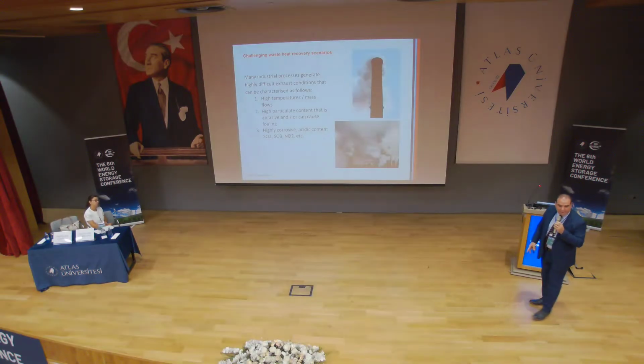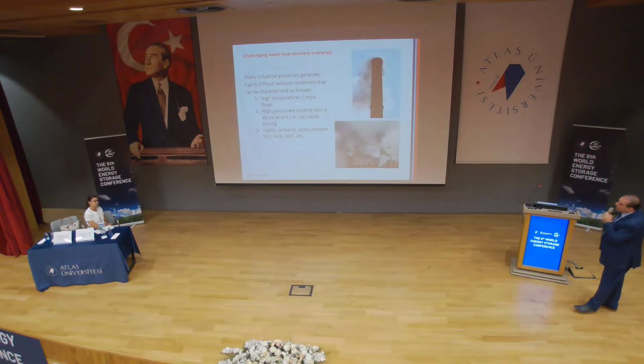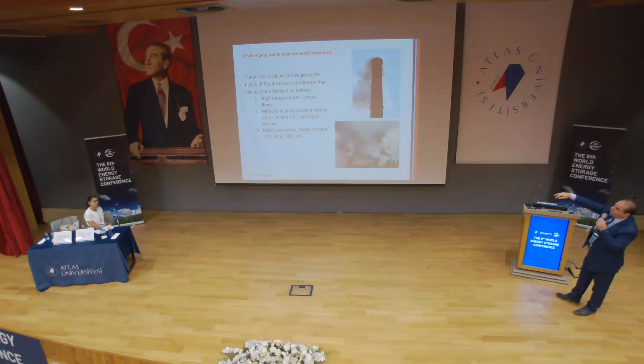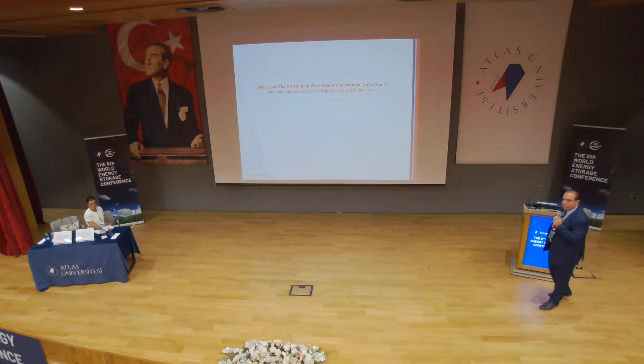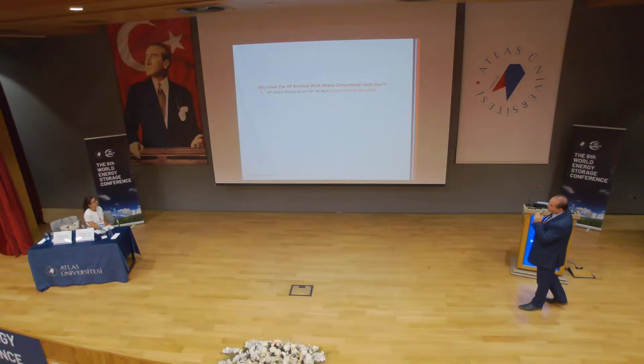So as scientists and engineers, we have to do something to address that. We use this technology to address them, because we can keep the wall temperature inside the heat exchanger uniform in the hot region, for example, meaning I don't have cold spots. When you have cold spots, you end up with acid condensation. We don't have that here. The same goes for the colder section. Having a uniform temperature in both the hot and cold regions is a huge advantage.